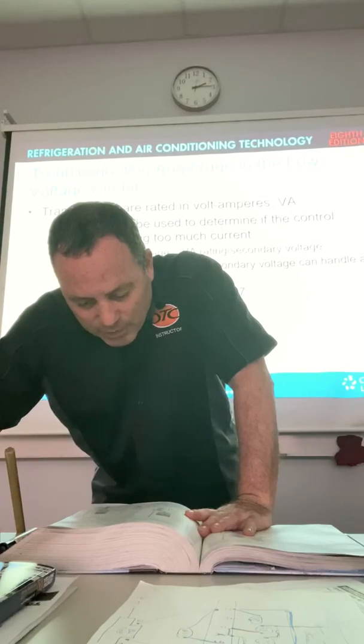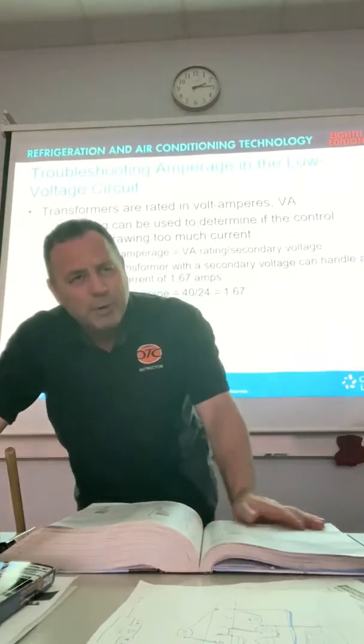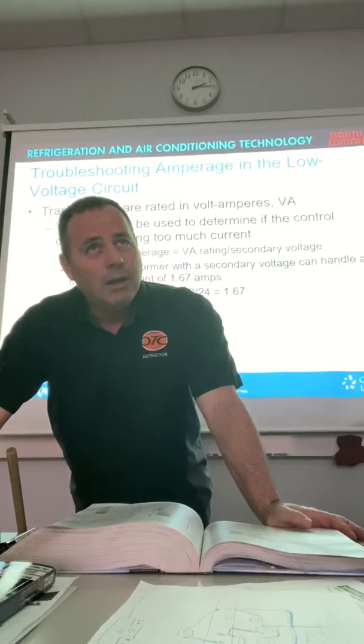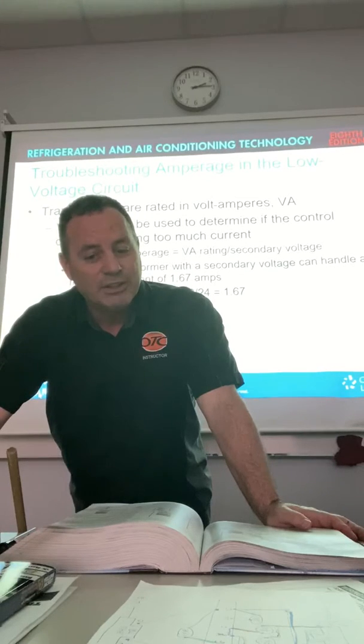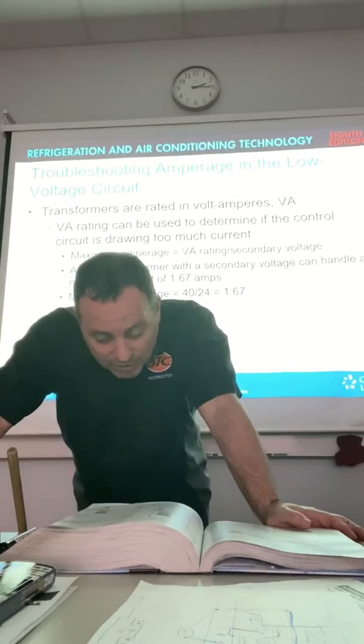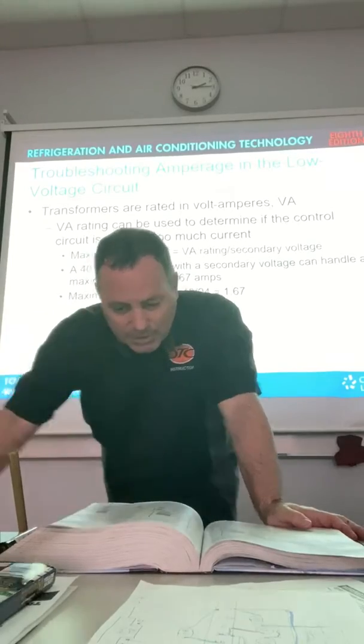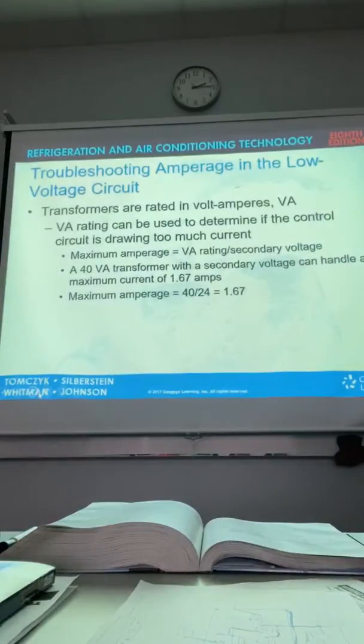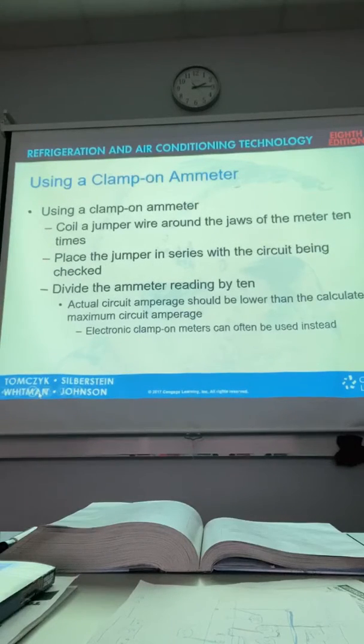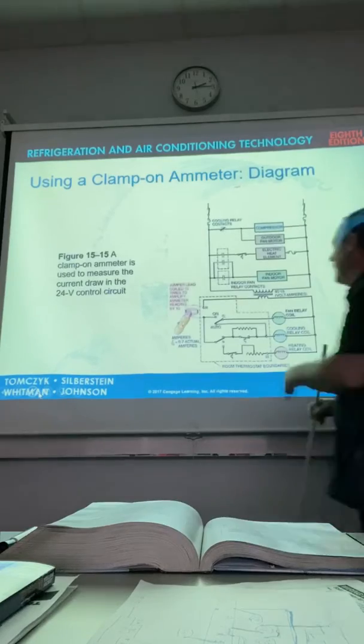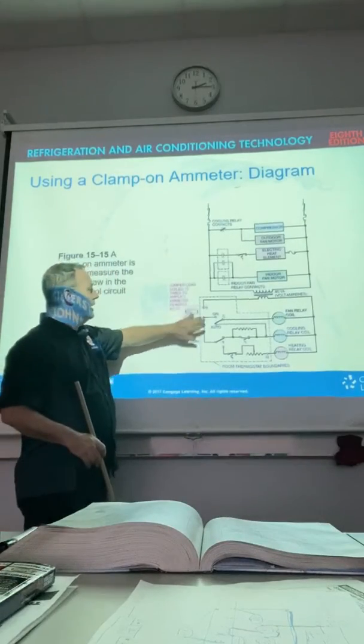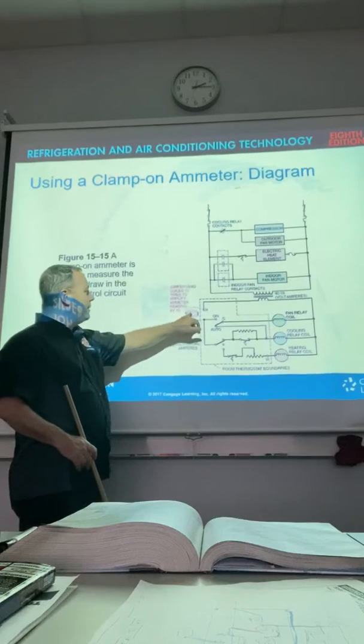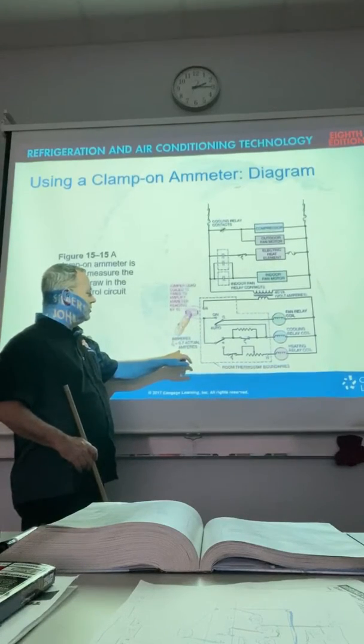Now, how can you know what it's drawing? Well, before we did the ten wrap with your ammeter for the W, the heat last week, in the controls, so we could set your heating anticipator. Well, let's look at this for a second. Your book says to use your clamp meter, and we're going to do the 10 wrap. So right here, we're going to take R, the other side of the circuit, wrap it 10 times, and see what it says.